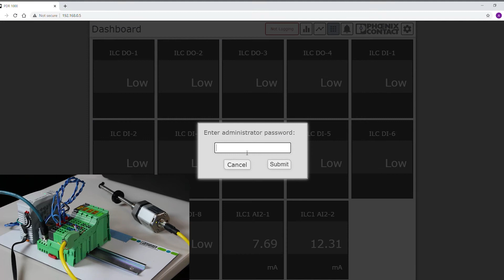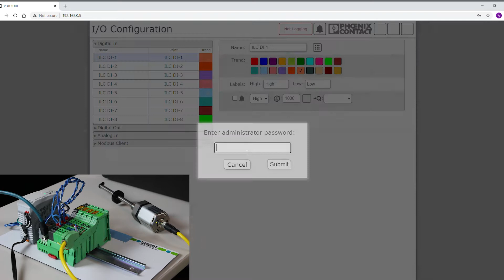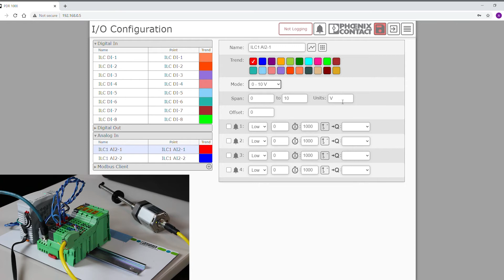So this is kind of what our home screen looks like, but from here we need to further configure our analog I/O. In our case, this is a 0 to 10 volt device, so we set that up. Right underneath where it says mode, we have something called span—this is where we can scale what our analog is and redefine that value. So if I wanted to change that to millimeters and say 1 volt equals 10 millimeters and I've got 100 millimeters total, this is kind of where we set that up.